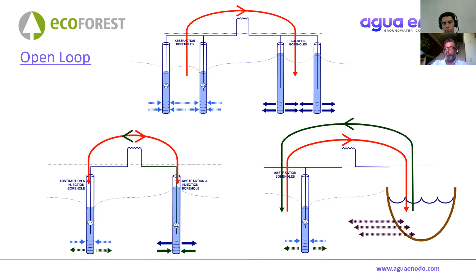Open versus closed loop: just a few highlight points. These are rule of thumb opinions, but open loop tends to have intrinsically higher risk to the project than closed loop. The main reason is that we can't know what an abstraction borehole and injection borehole will achieve in terms of sustainable yield before we've actually drilled it. We may have an excellent driller, an excellent borehole design, but still fail to achieve the flow of water we want from that well in a given location.